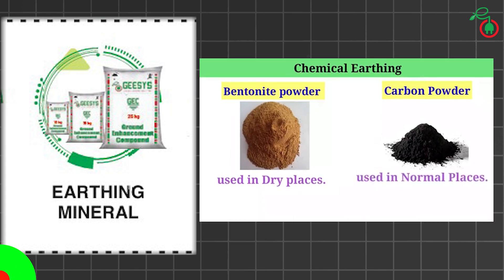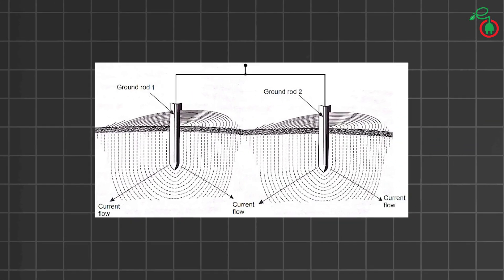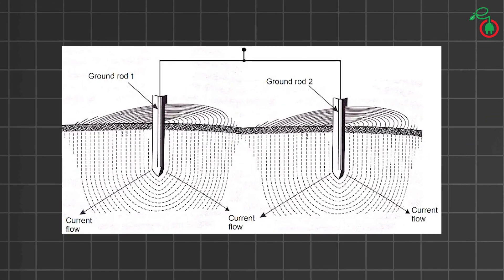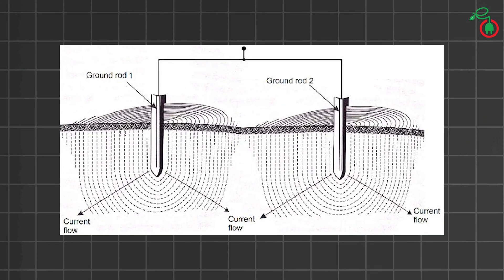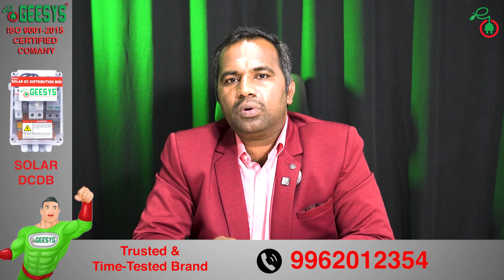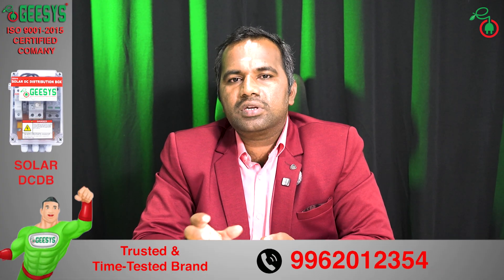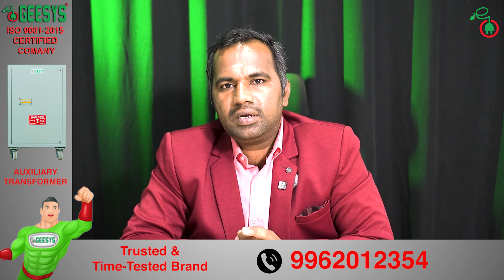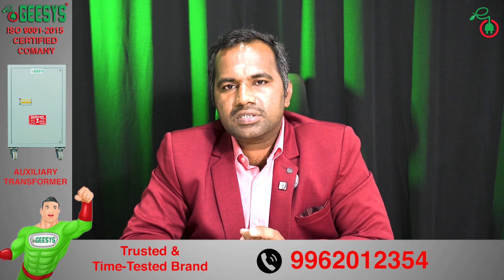Another important point is the distance between earth pits, which should be kept at more than two times the length of the earthing electrode. For example, if you have an earthing electrode of 3 meters, then 3 multiplied by 2 equals 6 meters — so from one earth pit to another, you should keep a minimum of 6 meters distance.